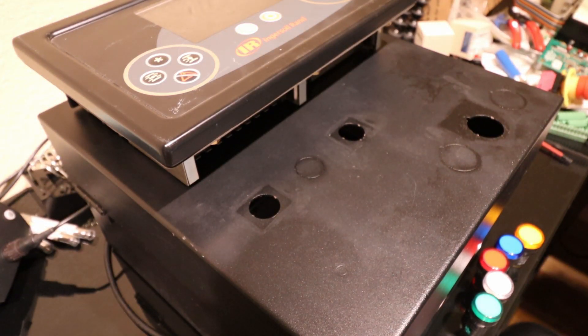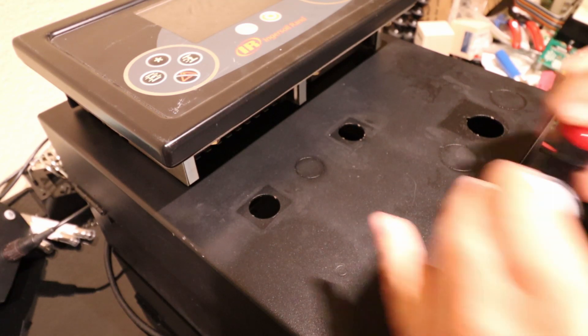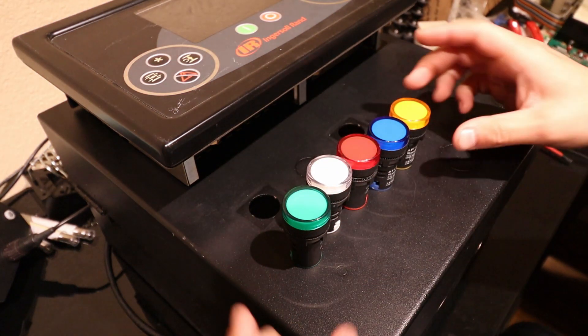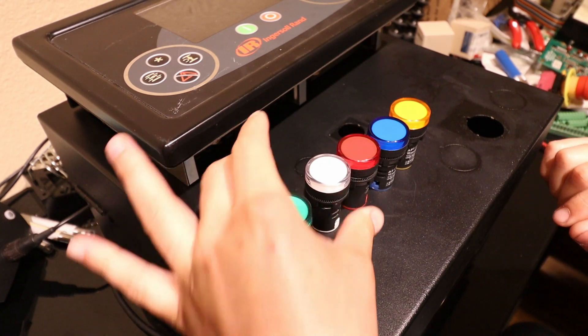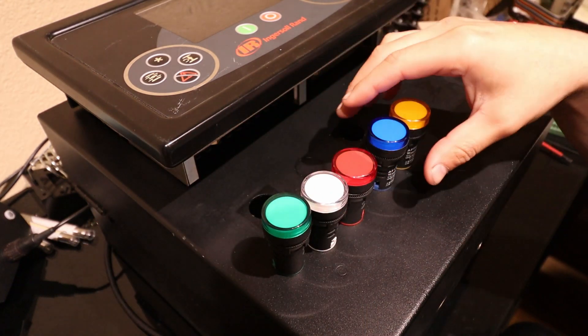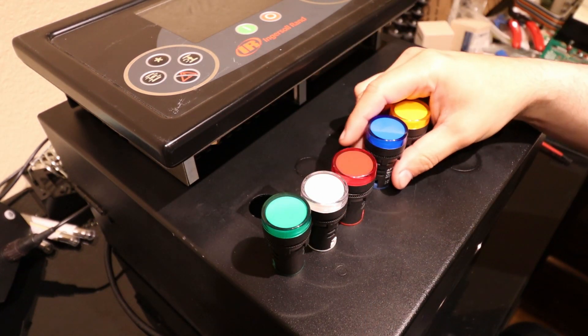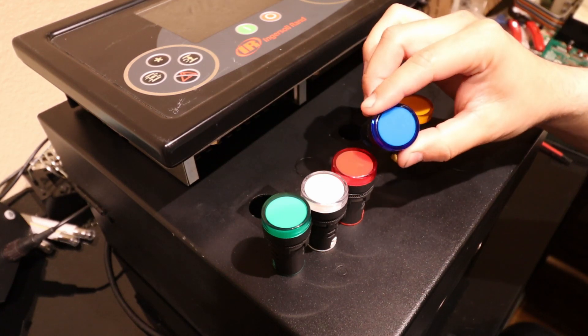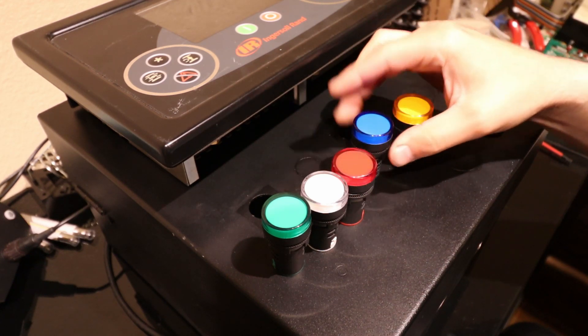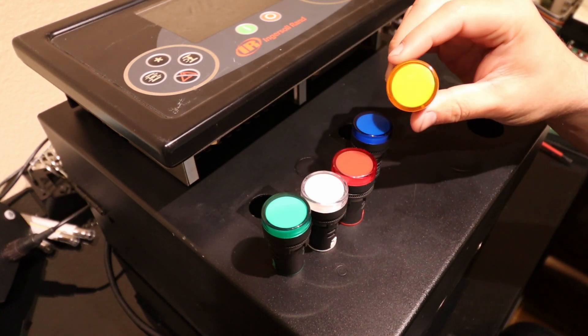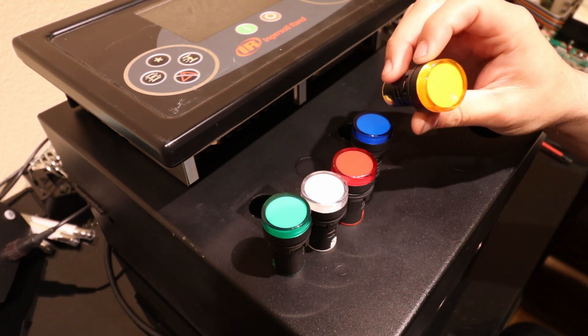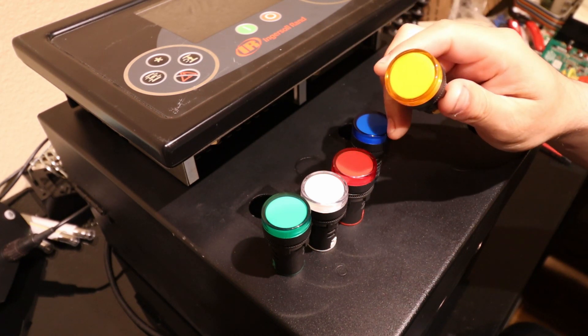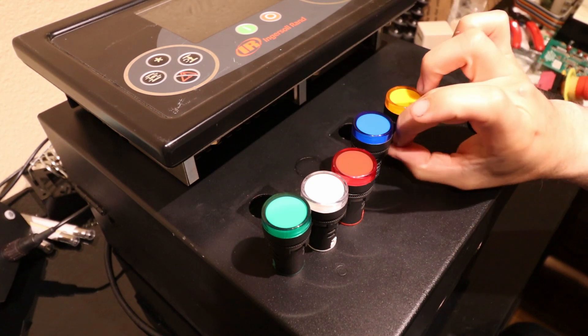We're going to size up the controller to the box that we're going to be using. We're also going to put our 120 volt indicator lights on top. Normally these will be used to show that 120 volts is being sent from the controller to a solenoid of some sort, either the contactors or load solenoid or condensate drain, basically solenoid valves, and we're going to use them to show that the controller is actually trying to do these things while it's running.